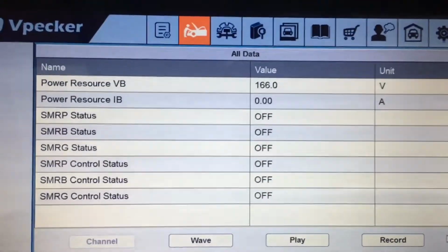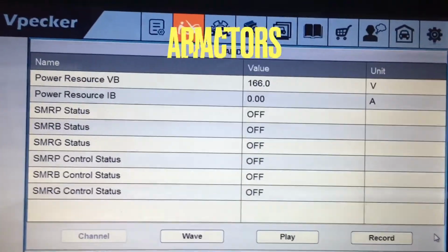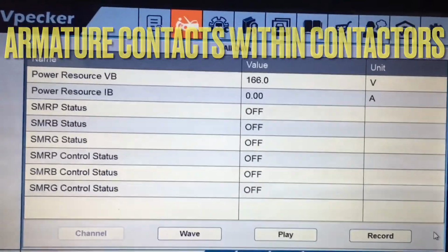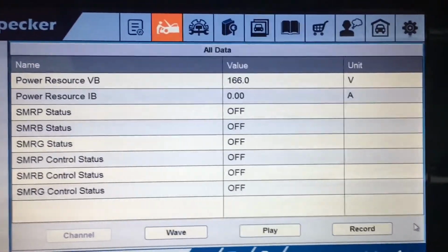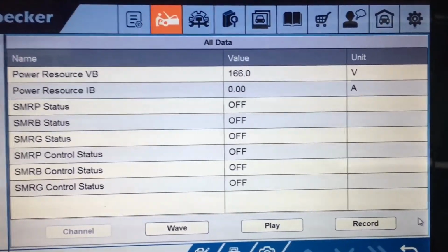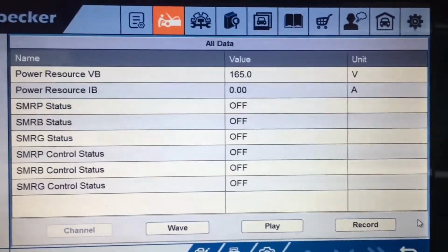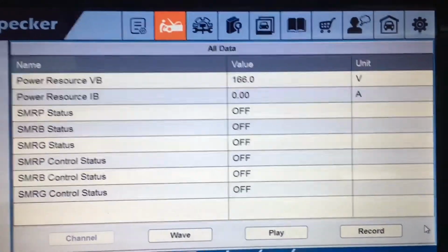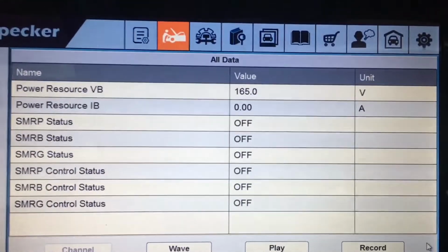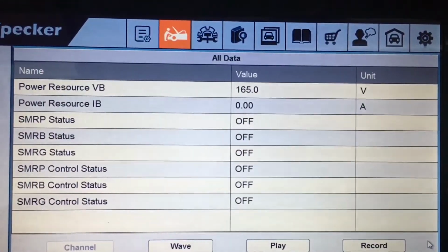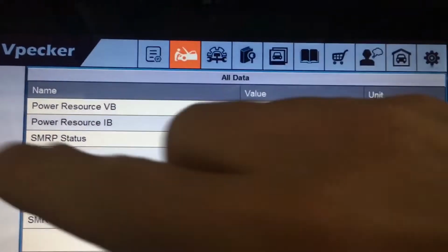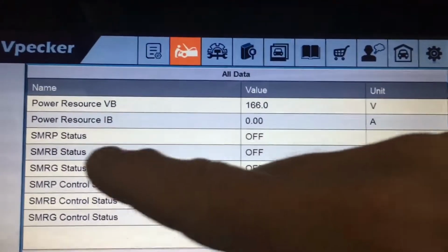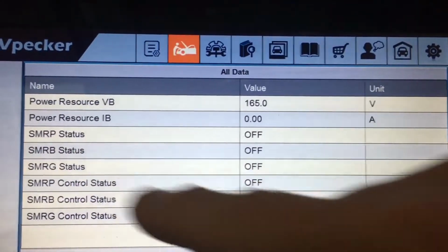What's the difference between a relay and a contactor? I don't know, I keep it simple. Basically anything above 50 amps in my mind is like a contactor, anything below that, a relay. You'll find a million different definitions, guys, but they're basically high current relays when I refer to a contactor, even though the data here clearly calls them system main relays.